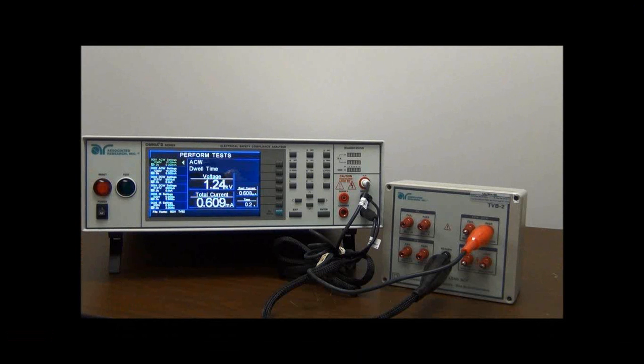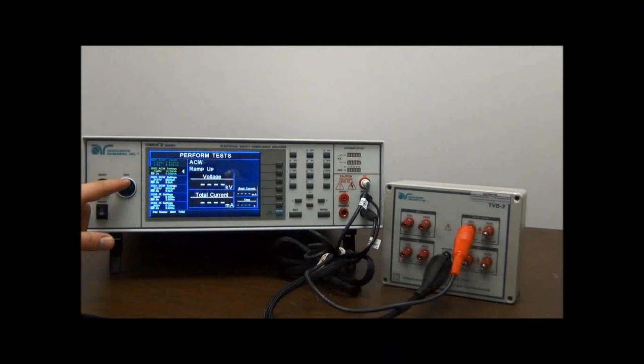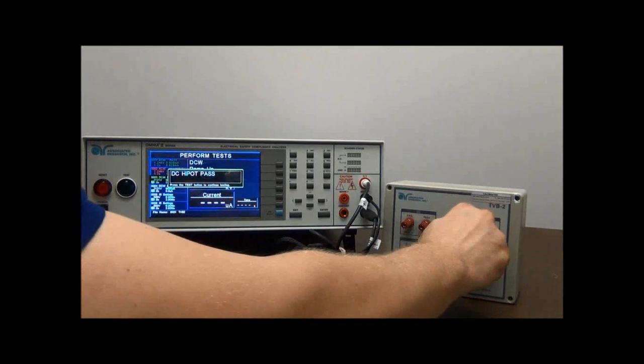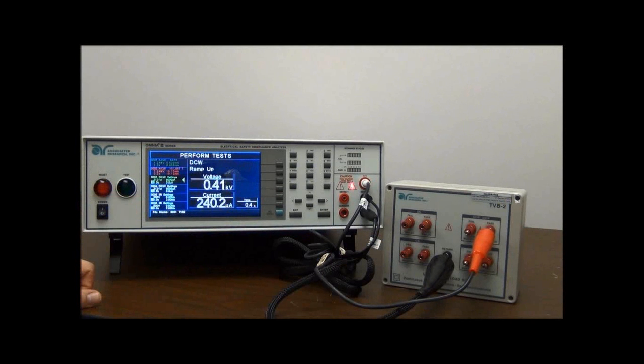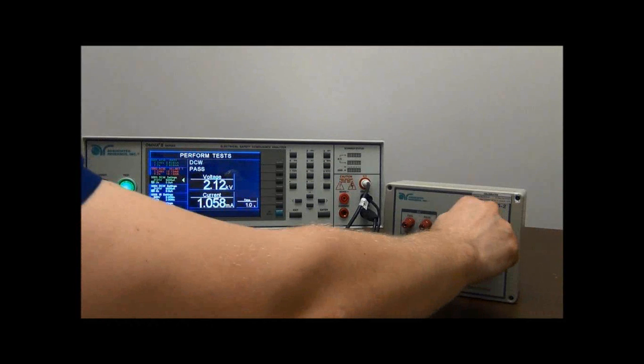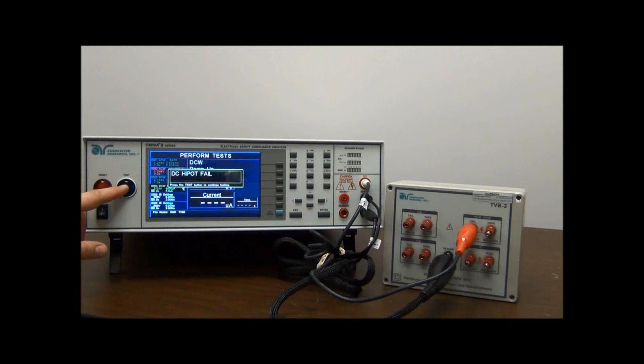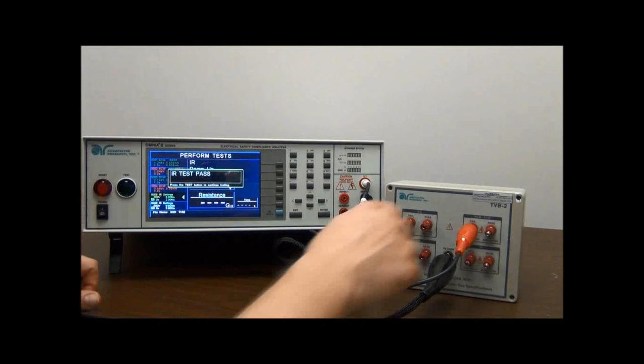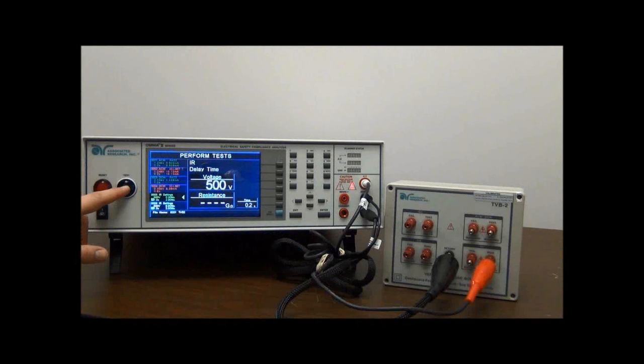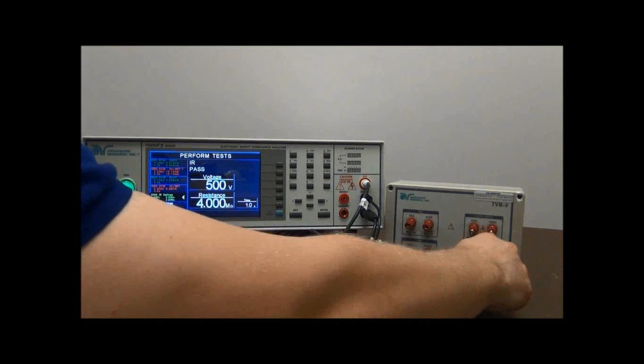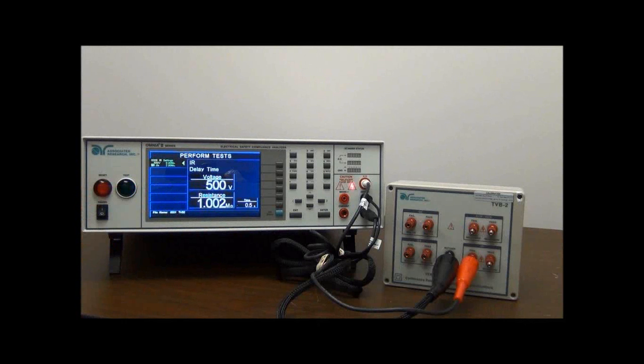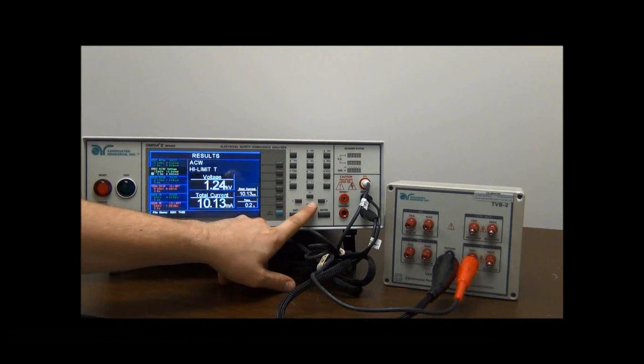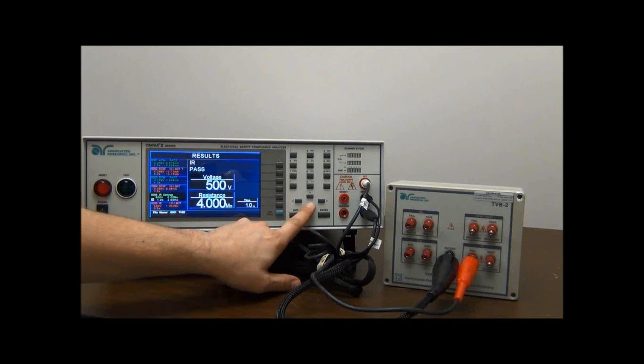Here we have the AC HiPOT pass, and then the next connection, we're going to clip the high current lead to the fail port of our load box. This should result in a failure, a high limit failure, meaning that the current limit has been exceeded. Next is the DC HiPOT test, pass condition, and then followed by a DC HiPOT fail condition. So this should result in a failure, meaning that, again, the current level has exceeded the threshold that was set. The next test is the insulation resistance test. Again, you can see the difference in the result is a high resistance value. And then we have our insulation resistance fail test set up to show that the test has actually failed, and the resistance of your product's insulation has come out to be lower than the value you want it to be.